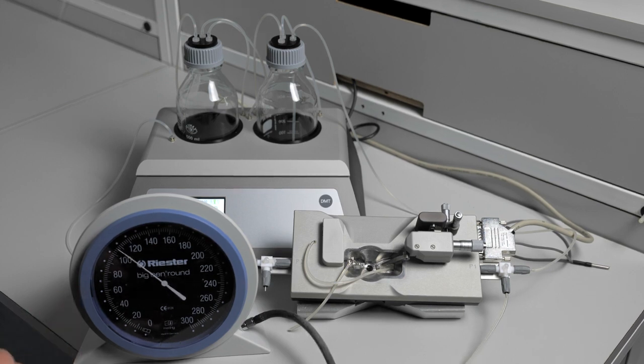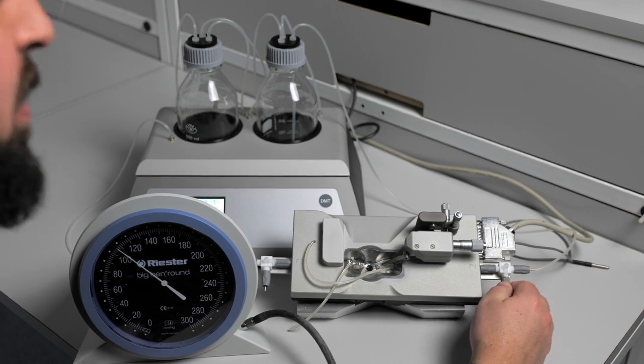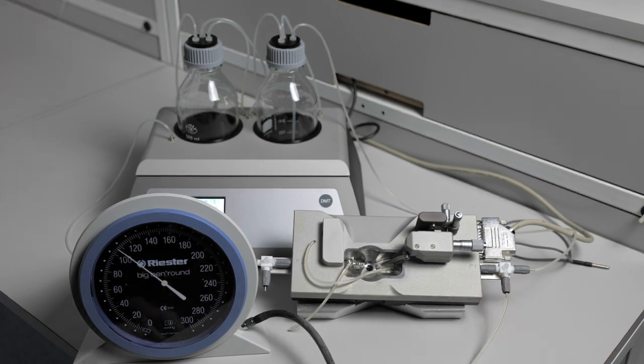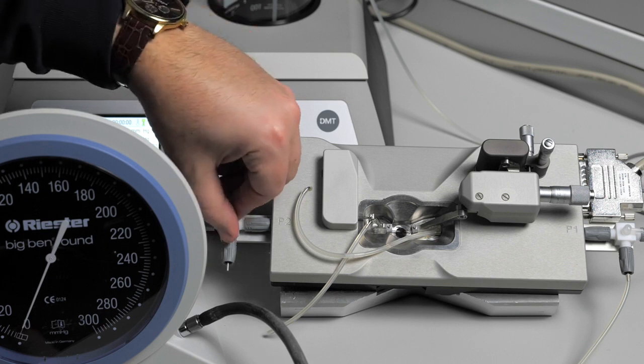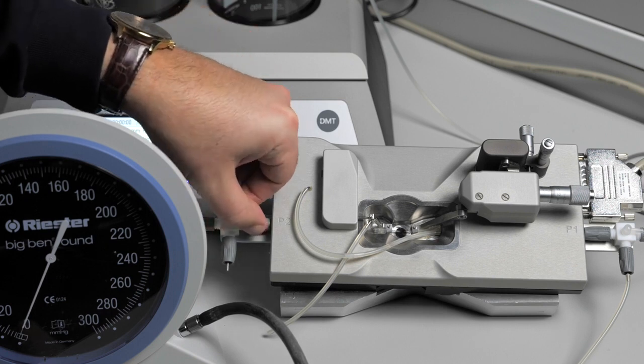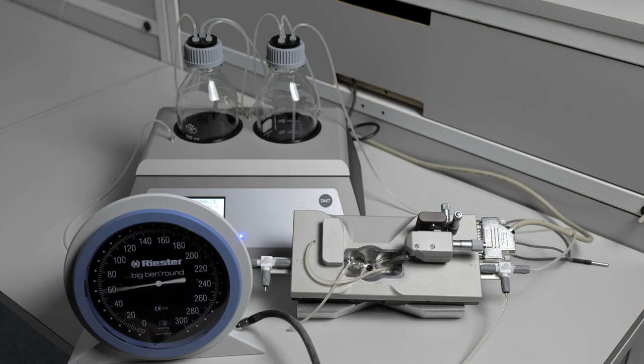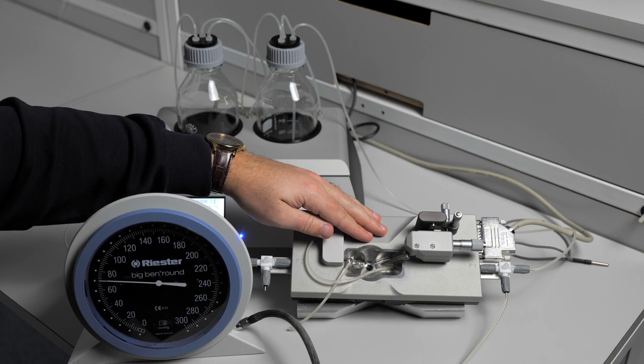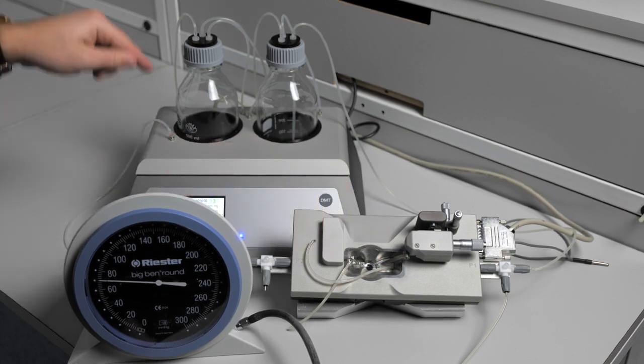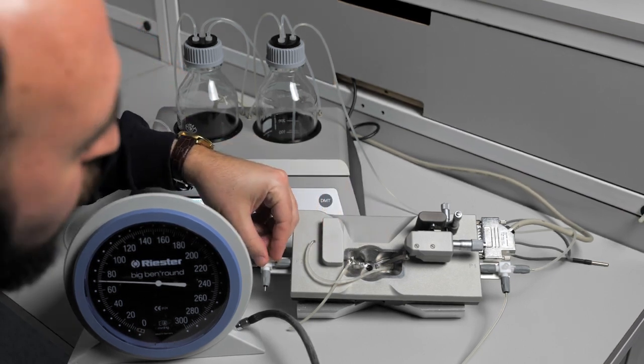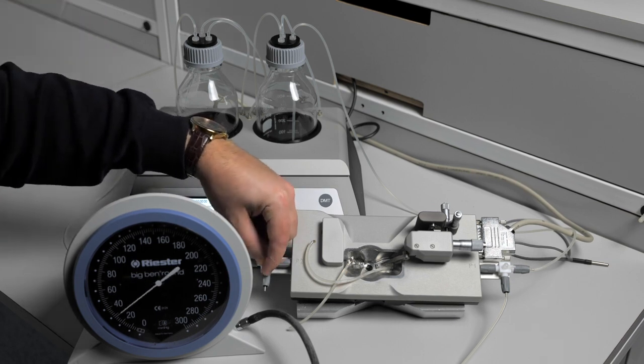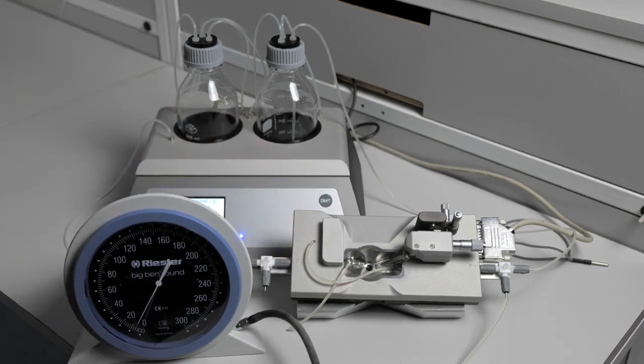If the pressure falls after you add this pressure, you can check and make sure that the plastic piece is securely tightened. If it is tightened and you still have your leak, then you need to replace your three-way valve. If you close the P2 three-way valve to the chamber and add pressure and it holds steady, then you know that your chamber is not the cause of your pressure leak and that the leak is after the chamber. Open the P2 three-way valve and you see that we have our pressure leak.